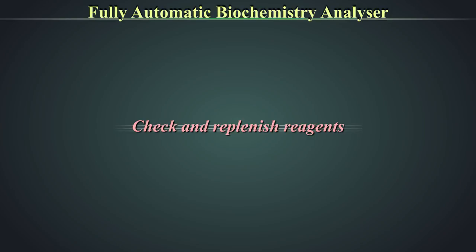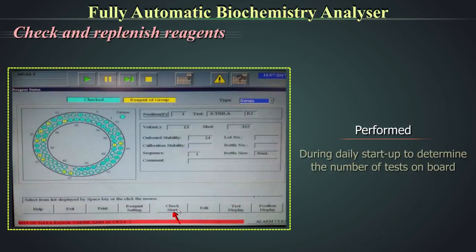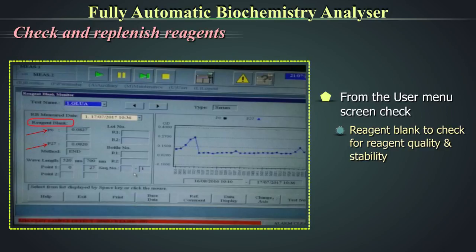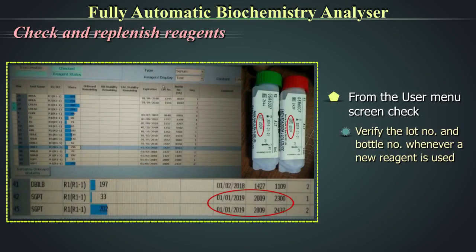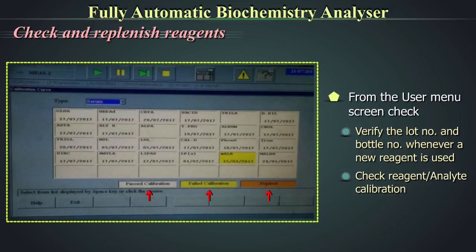A reagent check should be performed during daily startup to determine the number of tests on board and to update the status of the reagents. From the user menu screen, check the reagent blank for reagent quality and stability, reagent volume for adequacy so processing is not interrupted, and date of expiry of the reagents. Verify the lot number and bottle number whenever a new reagent is added. Check for reagent calibration.